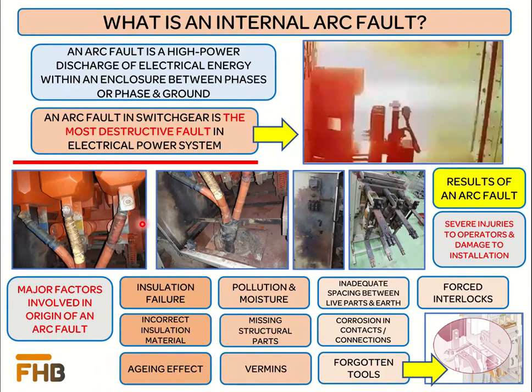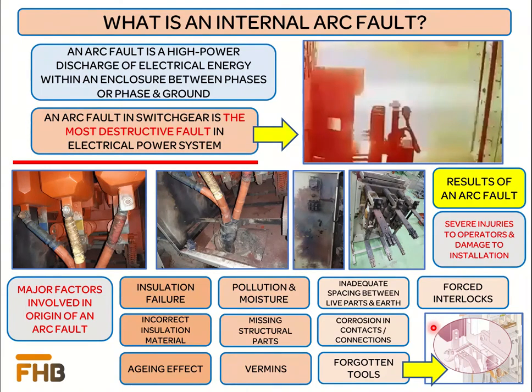Arc faults are also initiated due to damaged or corroded wires and wire terminals. During the commissioning process or maintenance period, it is recommended that the switchgear be cleaned thoroughly and all contamination from installation or maintenance work be removed. Any leftover fasteners or forgotten tools will result in the initiation of an arc fault. All removed partitions and covers in the busbar and circuit breaker compartments must be remounted. The integrated mechanical interlocking system present in switchgear prevents operator access to different switchgear compartments when energized. Any attempt to bypass the interlocking system may damage it and the consequences can be severe in the event of an arc fault.